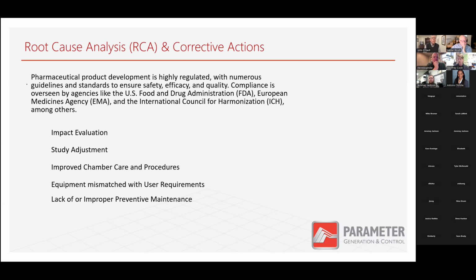It's not important just to get your chamber back up and running. It's very important to document all the steps that were taken to get it back up and running, as well as the steps you're going to take additionally to prevent it from happening again, and sometimes even a contingency plan to deal with it happening again.